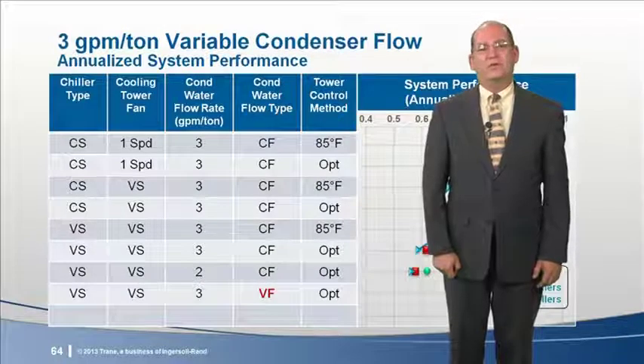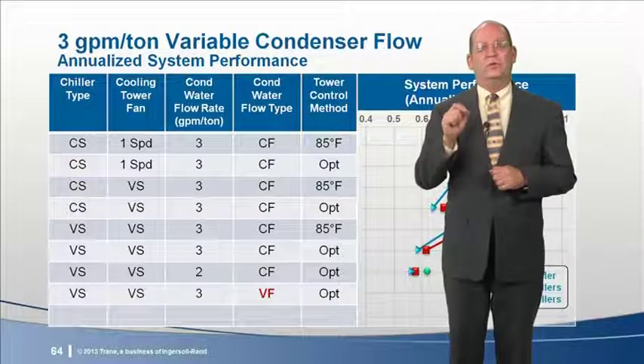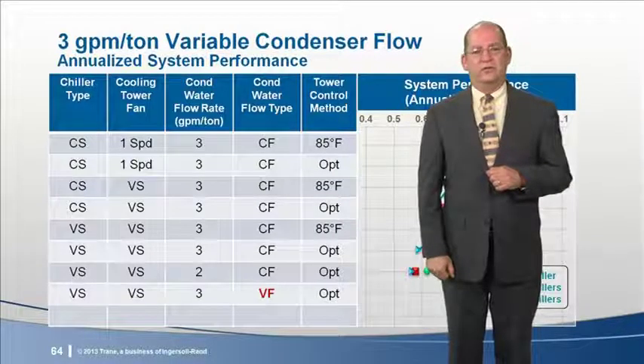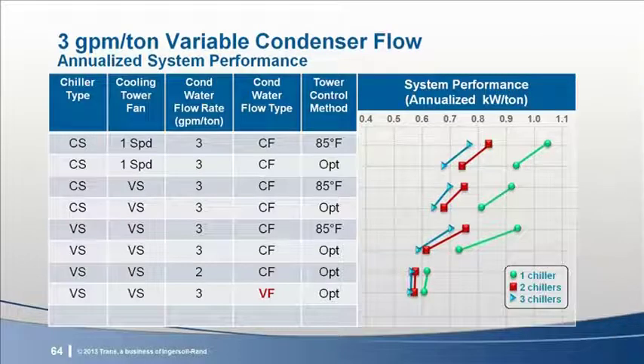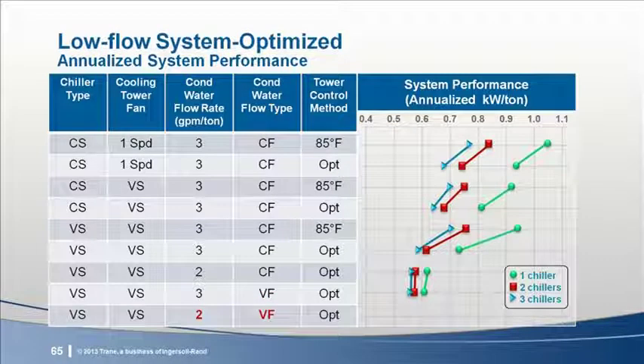Now let's put a variable speed drive on the condenser water pumps of a system using the older 3 GPM per ton design flow rate. There are some savings due to proper control of the VSD, but the system performance is very similar to that of a system that was designed with reduced flow and used a constant speed condenser water pump. So design teams can choose to design with lower flow rate and simpler controls, or higher flow rate and increased complexity. Results are similar.